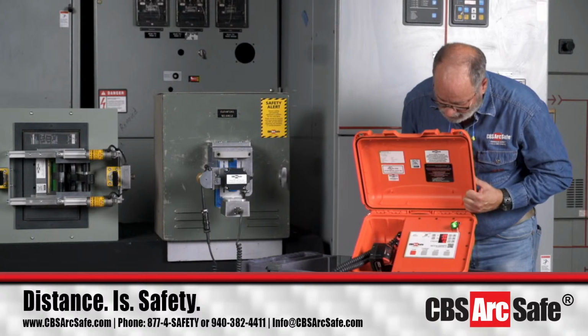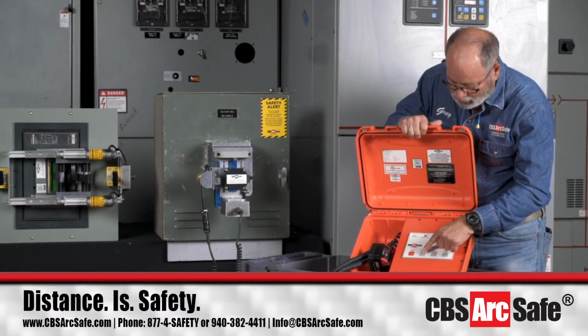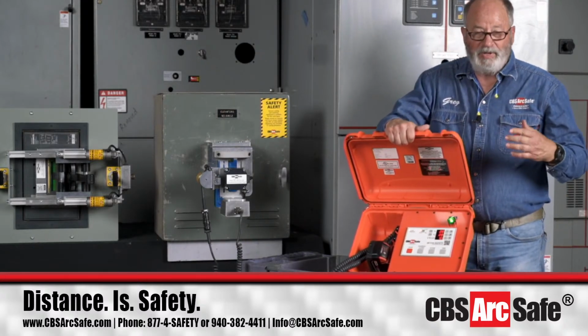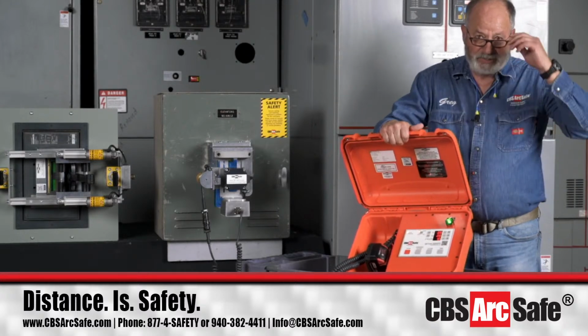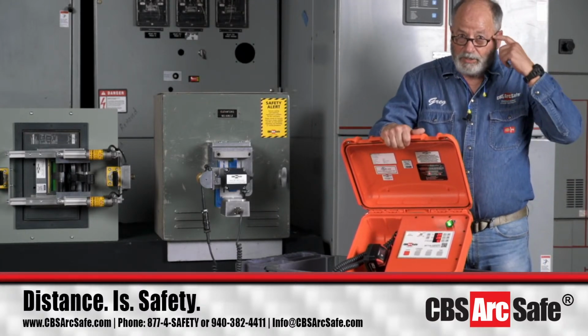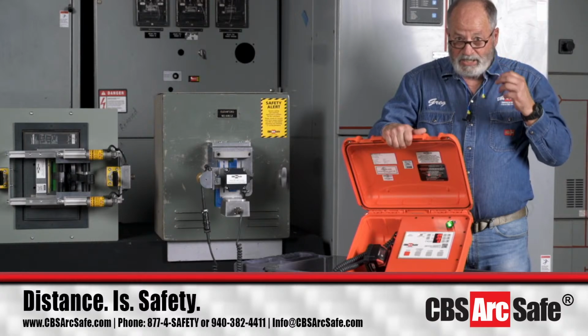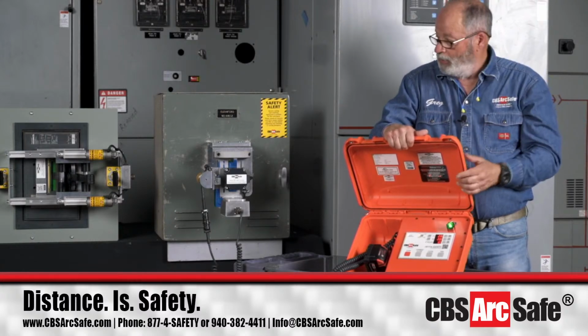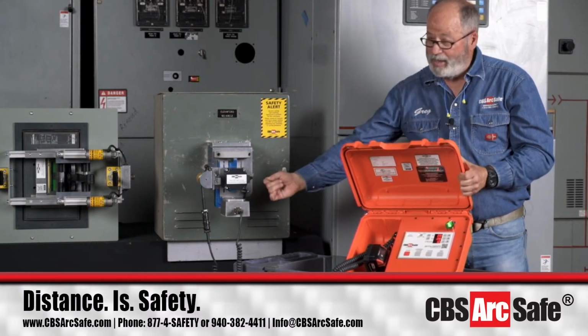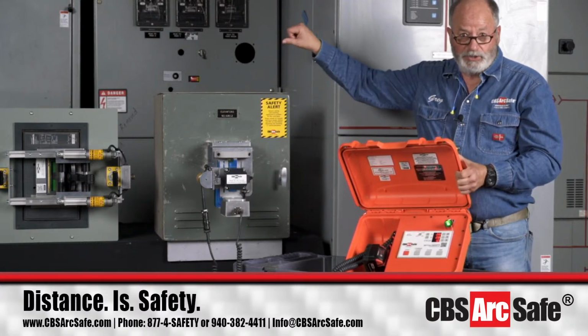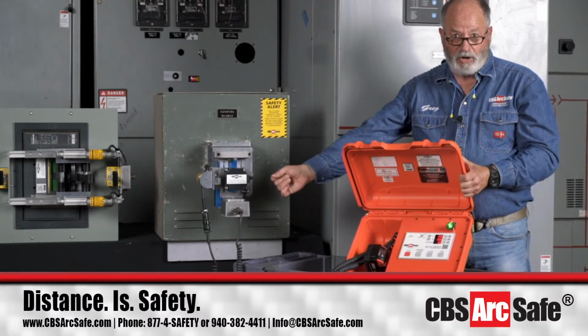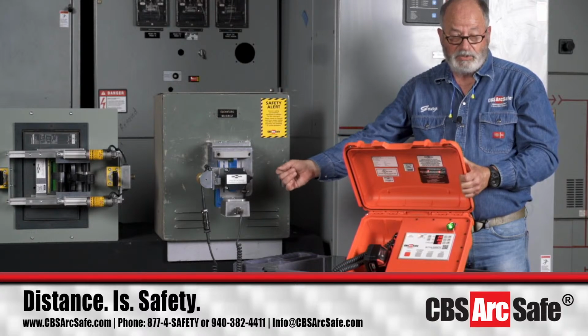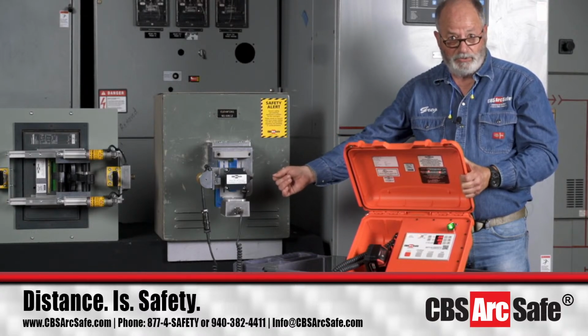We have AR off. We're going to push charge close once. The reason we have this button labeled charge close is this: breakers like your first generation GE AK breakers, where you would move this handle up one time and bring it back down to the bottom, you're charging the spring and closing it all in one shot. So that's the reason it's labeled charge close.